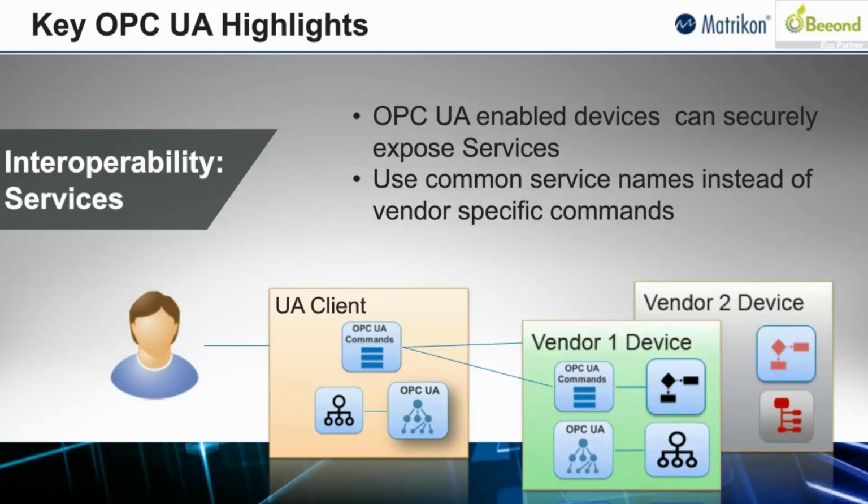So just as below, you can see that it's got the OPC UA data structures, or the information model, from a data relationship perspective. The same way, you're also exposing in a standardized way, let's say, the verbs of the device. If the data relationships are the nouns that store information and say what the relationships are, the commands would be the verbs, which say what you can do with that device, or what that device can act on. So when the clients connect, just as they can understand and work with the data relationships, they can also call on various functions that the device would perform.